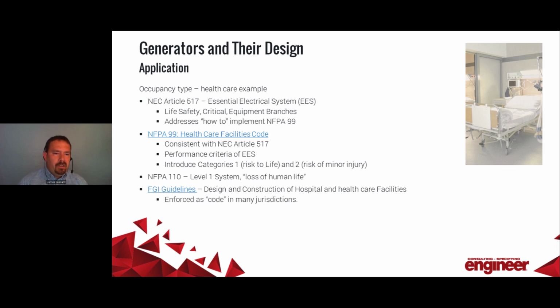And NFPA 99, which is the Healthcare Facilities Code, is generally consistent with 517. In the past, there were some discrepancies, but through the code revisions, they've worked through a lot of that. It lists the performance criteria. Like I said, it sets the criteria, and then the NEC defines how you implement that. In 99, they introduce the concept of two different categories for systems. The first being preservation of human life. Is there a risk to human life? That would be a Category 1 system, and a Category 2 system is a risk of minor injury. So there's a distinction there, and there's separate requirements for each of those two system categories.